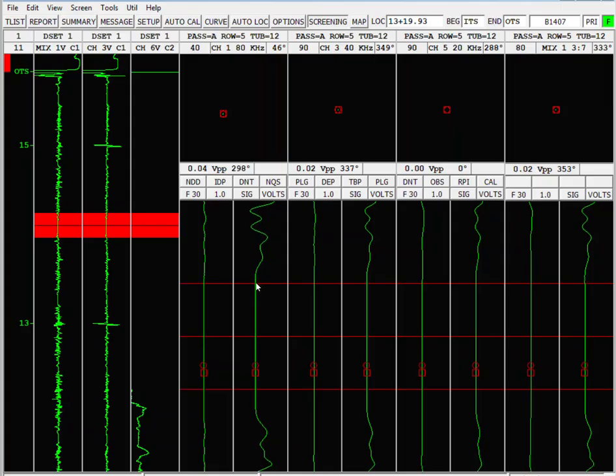So if you're on a job and there is a separate acquisition team that's collecting the data, and you start to see dead spots like this, then it's time to go over to the data acquisition team and talk to the probe handler, show them examples of this data, and explain that efforts must be made to always keep the probe moving. Otherwise, they're going to be retesting a bunch of tubes unnecessarily. If you can use a mechanical probe driver, if that's in the budget, that is an easy way to prevent this type of bad data.